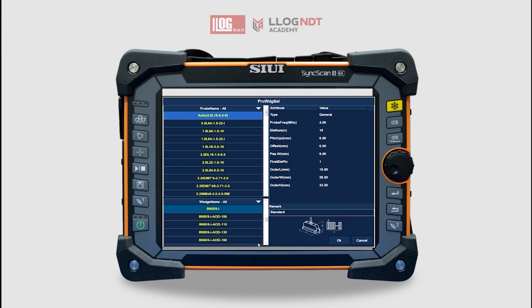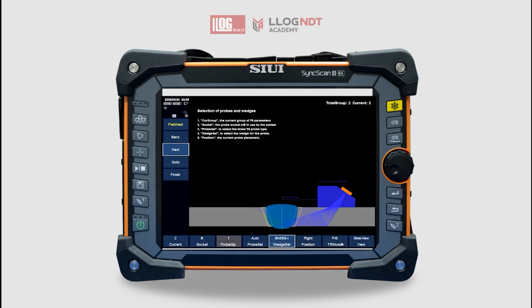Select the transducer model. Select the wedge and define the transducer position on the right side. Then press Next. Select shear waves, then press Next again. Set the angle range from 40 to 70 degrees with a step of 0.5 degrees. Set the active elements from 1 to 16 and set the focal depth to 20 millimeters.